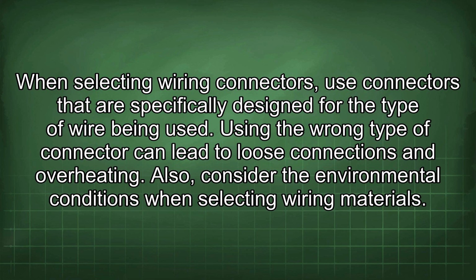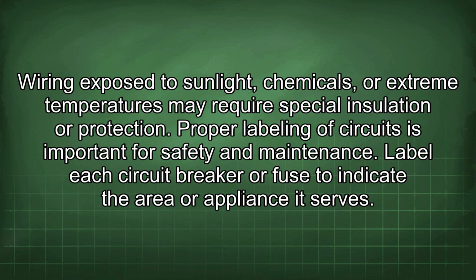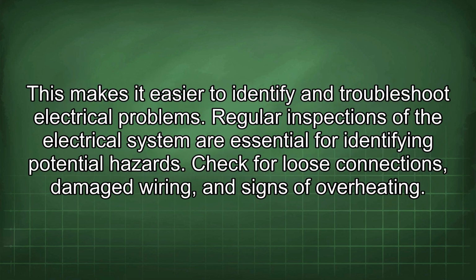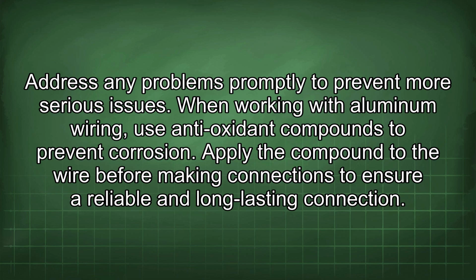Also, consider the environmental conditions when selecting wiring materials. Wiring exposed to sunlight, chemicals, or extreme temperatures may require special insulation or protection. Proper labeling of circuits is important for safety and maintenance. Label each circuit breaker or fuse to indicate the area or appliance it serves. This makes it easier to identify and troubleshoot electrical problems. Regular inspections of the electrical system are essential for identifying potential hazards. Check for loose connections, damaged wiring, and signs of overheating. Address any problems promptly to prevent more serious issues.